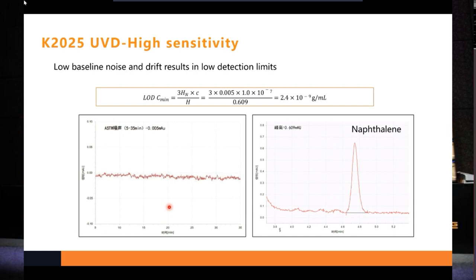The high sensitivity is achieved by using the improved optical design. The low baseline noise and drifts result in the low detection limits. And samples in low concentration can be detected with high sensitivity. We use the standard sample to check the limit of detection in this experiment.